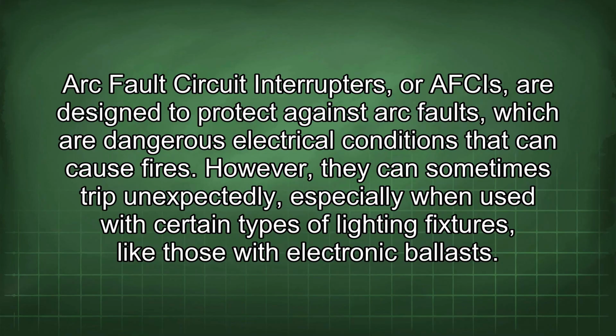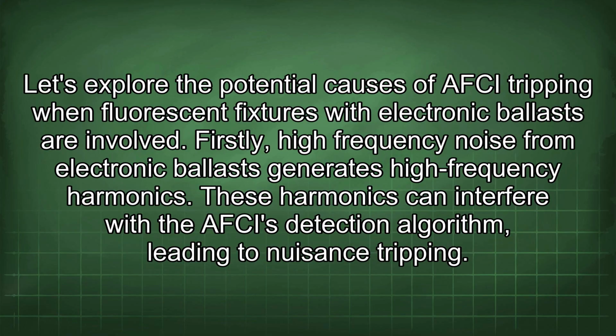Arc fault circuit interrupters, or AFCIs, are designed to protect against arc faults, which are dangerous electrical conditions that can cause fires. However, they can sometimes trip unexpectedly, especially when used with certain types of lighting fixtures, like those with electronic ballasts. Let's explore the potential causes of AFCI tripping when fluorescent fixtures with electronic ballasts are involved.